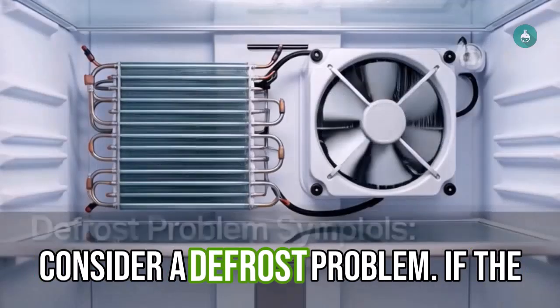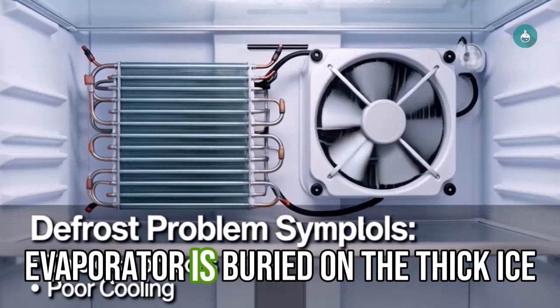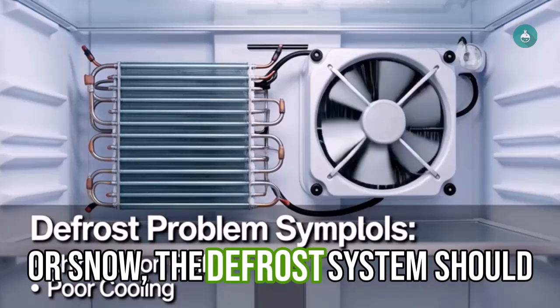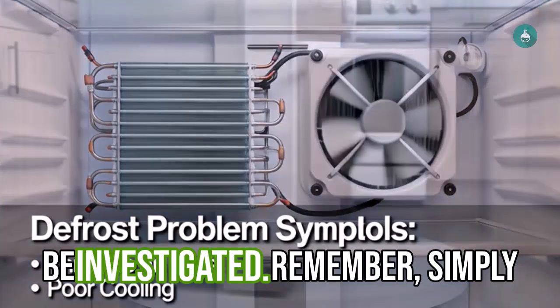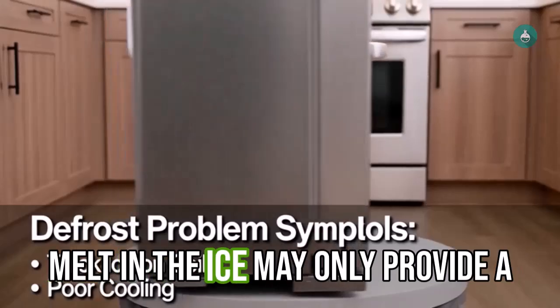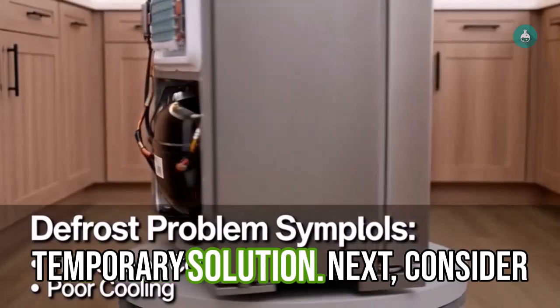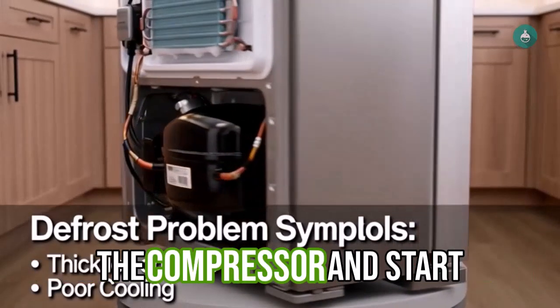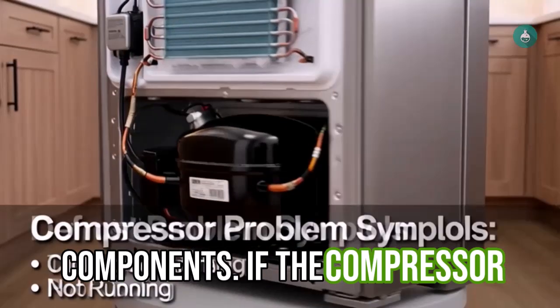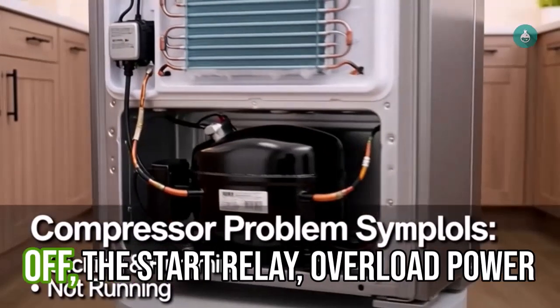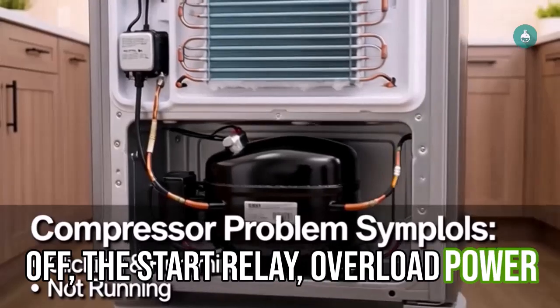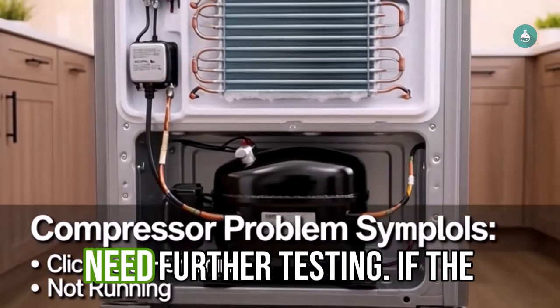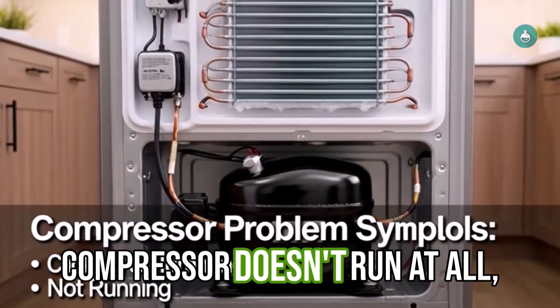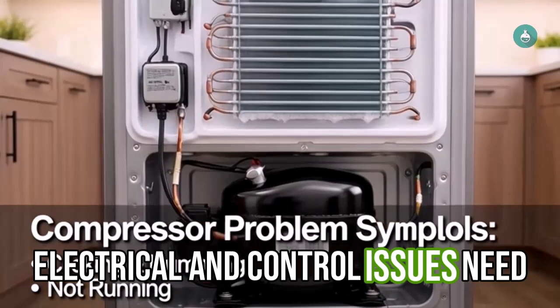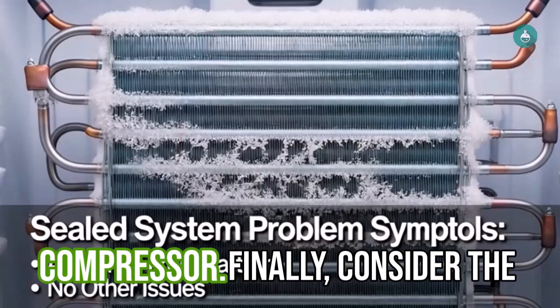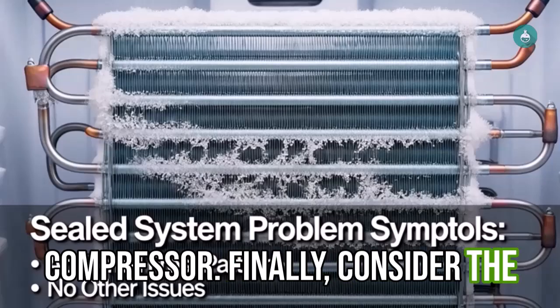Next, consider a defrost problem. If the evaporator is buried under thick ice or snow, the defrost system should be investigated. Remember, simply melting the ice may only provide a temporary solution. Next, consider the compressor and start components. If the compressor repeatedly clicks, hums, and shuts off, the start relay, overload, power supply, or compressor itself may need further testing. If the compressor doesn't run at all, electrical and control issues need to be investigated before replacing the compressor. Finally, consider the sealed system.